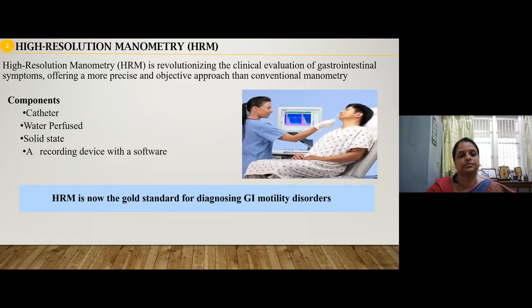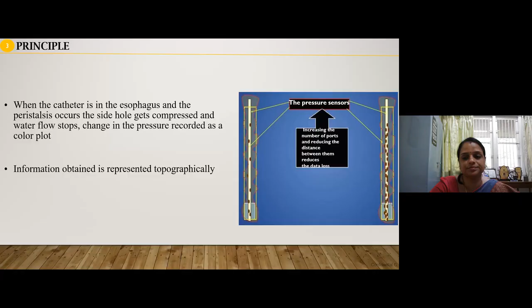Next slide, please. So what is the principle of manometry? I told you the catheter has sensors. This is a catheter, and you can see that these dots represent the pressure sensors. When the catheter is in the esophagus and peristalsis occurs, the side hole gets compressed and the water flow stops. This change in pressure will be recorded as a color plot, and the information will be obtained as a topographic color plot. The pressure changes detected by the sensors on the catheter are converted into electrical signals, which are then recorded, visualized and analyzed.